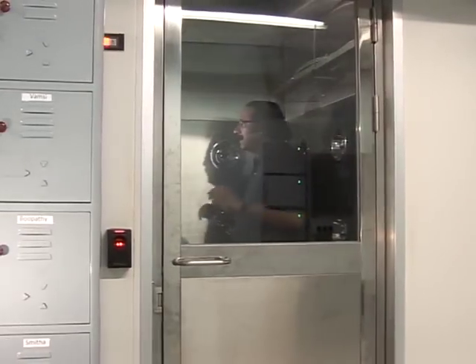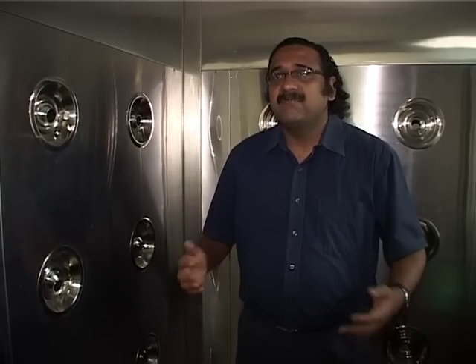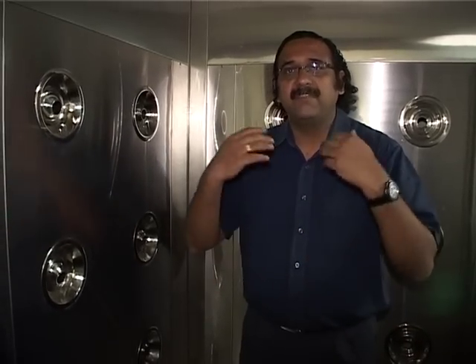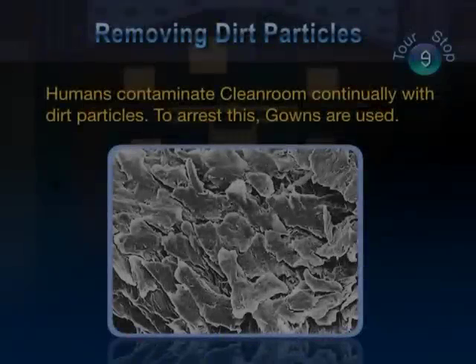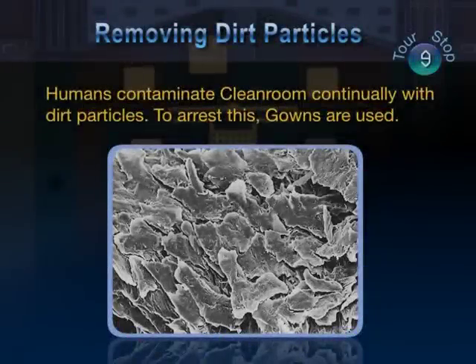So this is the air shower region. In this region, we start cleaning the contamination that is generated by the people. So now the loosely bound particles which are attached to my body and the clothes are removed by this air shower. From this region, we will move into the gowning area where we will confine the dust particles generated by the people within this gown. Since humans contaminate the clean room continually by shedding dirt particles, full body gowning is an important ancillary to the HVAC system.